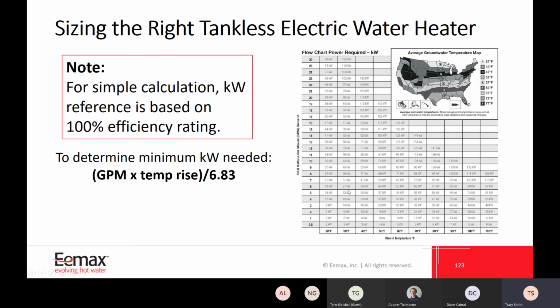Now, this chart does not apply to mini tank or Auto Booster - this is strictly for tankless electric hot water heating. So let's say we have a 2 GPM kitchen sink that we want to supply a hot water heater for, and we have a 60-degree rise in temperature, we need an 18 kilowatt heater. It's as simple as that.